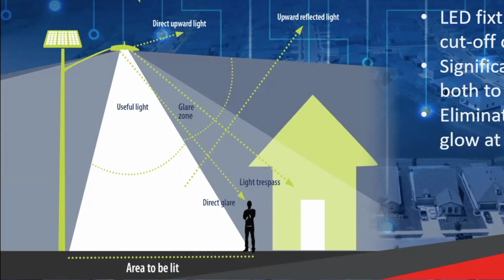John has asked, has there been any advances in controlling backwards spill light across residential and city roadways? Yeah, a lot has happened there, and predominantly I think that's been due to the fact that we've now got our dark sky compliant lighting. Previous to that, we've always done a great job with providing sharp cutoff, low glare impact lights. It's important to recognise we have actually two different types of LED optics available, and they're for different applications. So for instance, our street lighting LEDs are designed to provide only minimal rear spill to illuminate the footpath behind it. So there has to be some sort of backward light, but not too much. And mostly it's all about trying to push as much light asymmetrically, so that's left and right, and also forward to the opposing side of the street.